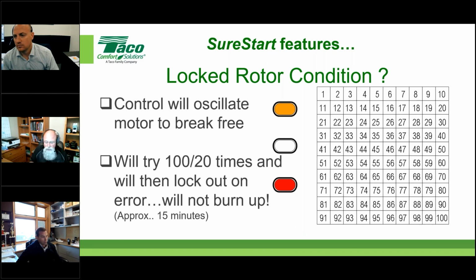You clean the power head up. You make sure the O-ring's in the right place. You put that thing back together. You repurge the air out of the circulator or the system, depending on how you have it piped and isolated. And then you start that baby back up. That resets the counter, and normally you take off and you're running again. You're not throwing pumps away at that point.